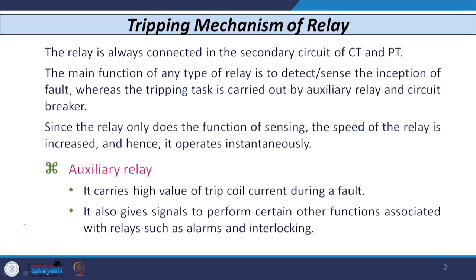Today we will discuss the basic tripping mechanism of the relay. We know that relay is always connected either on the secondary of CT or secondary of PT — we may use either CT or PT or both. The main function of relay is to just detect or sense the inception of fault, whereas the tripping task — isolation of the faulted part or section — is done by auxiliary relay or circuit breaker. Since the relay only senses or detects the fault, its speed increases and some relays may operate instantaneously depending upon the magnitude of fault current.